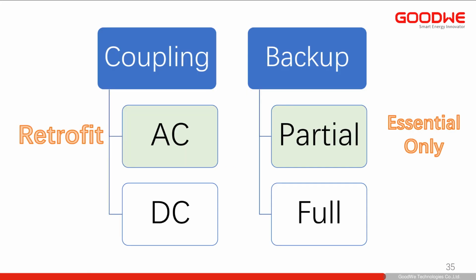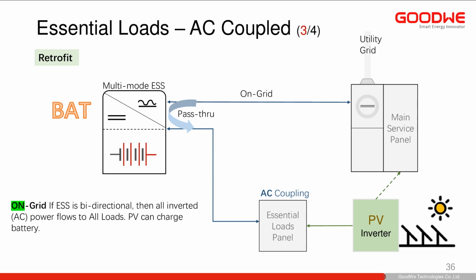Now we're going to look at a retrofit of essential loads. Here, the PV inverter, which was originally connected to the main service panel, is going to be relocated to the essential loads panel. Why are we doing this? Well, if the grid goes down, the PV inverter is going to shut down because there's no AC waveform anymore. So if we connect to the essential loads panel, we create our AC coupling and get our AC waveform from the battery inverter.